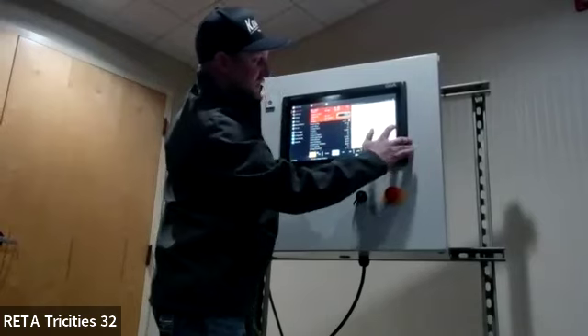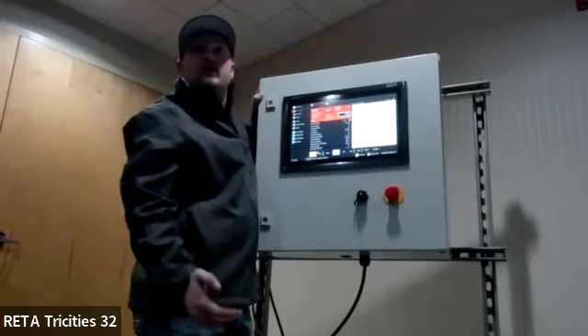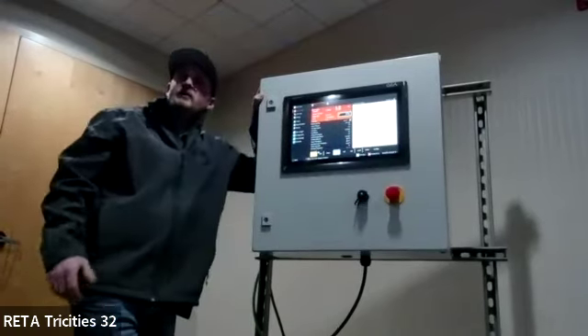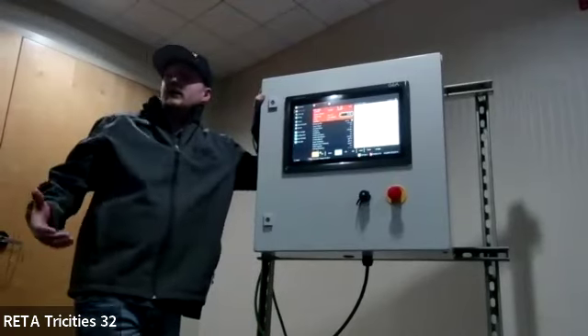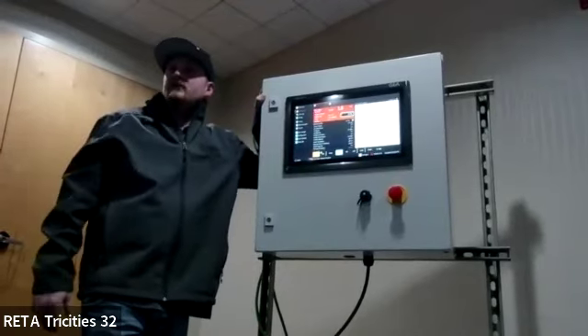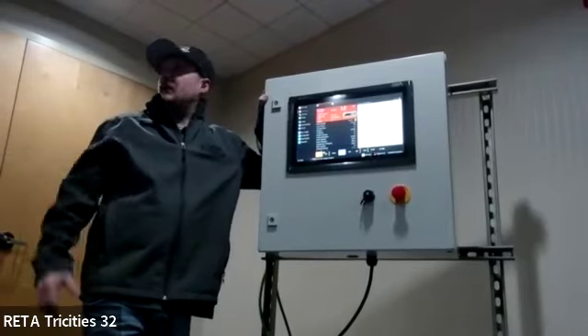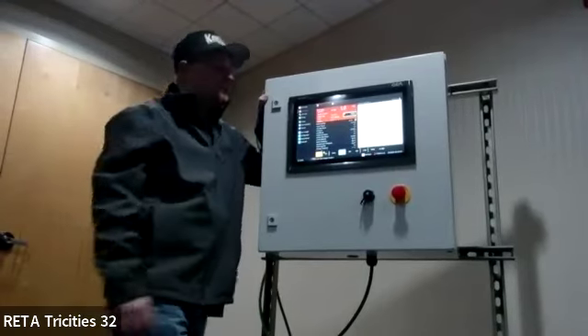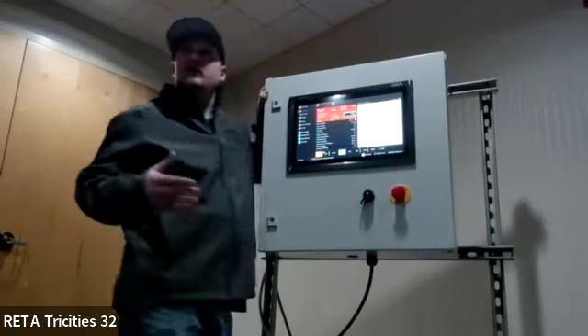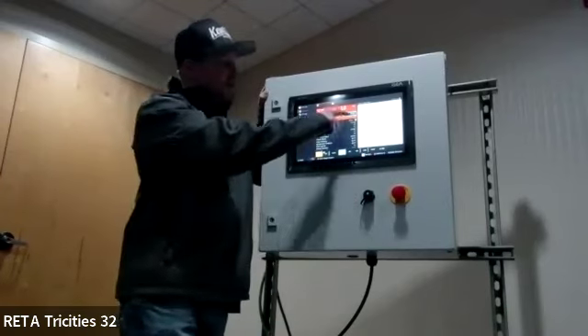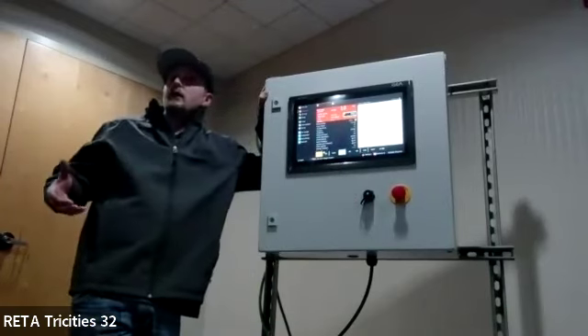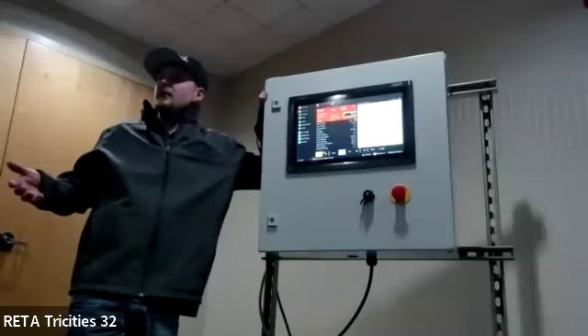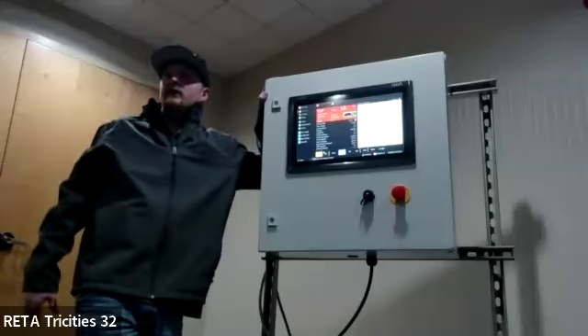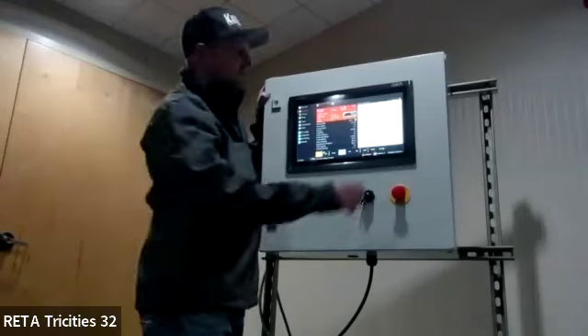You can also adjust the minimum and maximum capacity slide position. If you're having an issue with potentiometer or slide valve sticking, I would say at 80%, you can set it to maximum load 75%. On a VFD, you're running this on a drive, which this is set up for a drive right now, you want to run probably like a 20% minimum slide valve. You're not going to want to really run it at 0%.